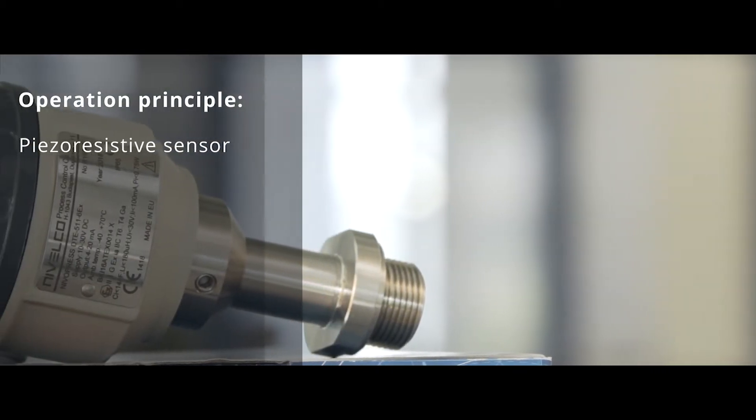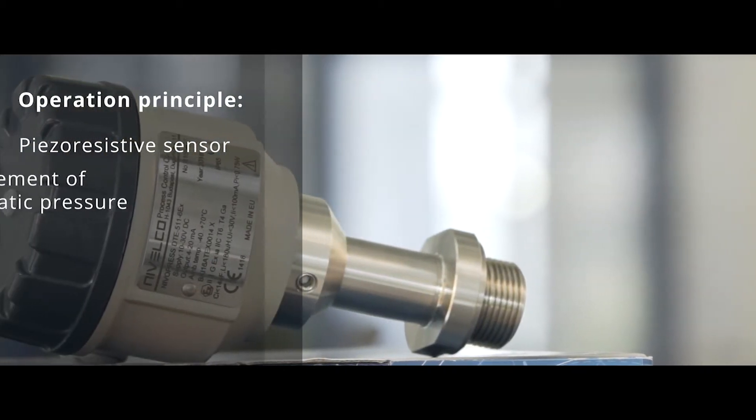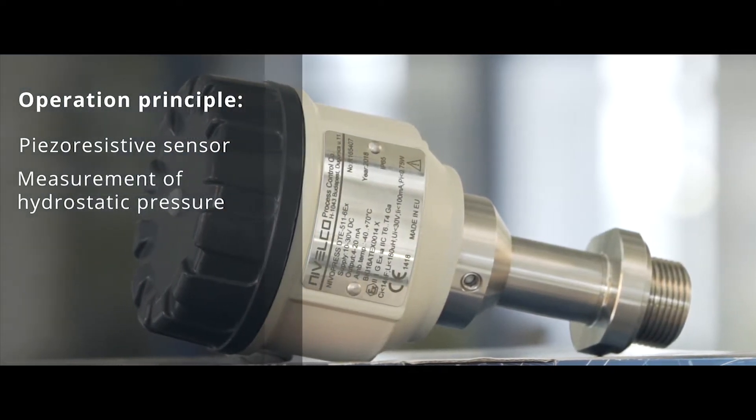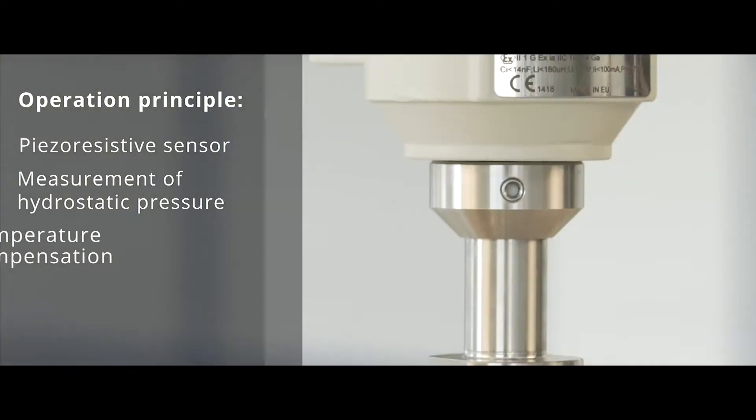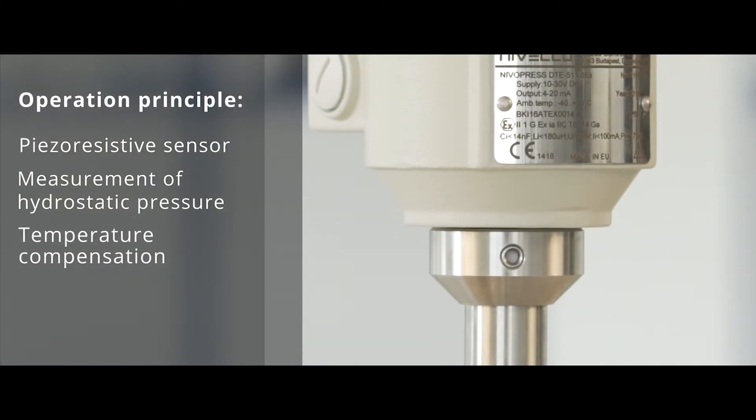Operation Principle: The piezo-resistive sensor of Nivelco's Nivopress DTE, protected by a stainless steel flush diaphragm, measures the hydrostatic pressure and compares that with the actual atmospheric pressure. The measured value may be temperature compensated.